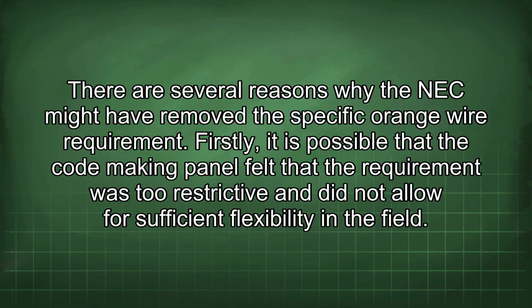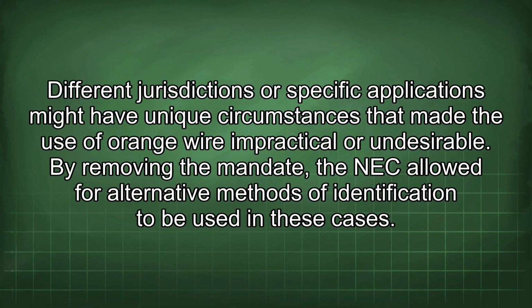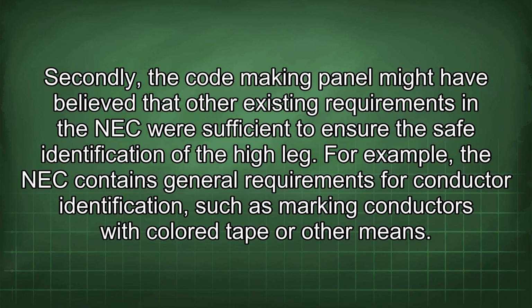There are several reasons why the NEC might have removed the specific orange wire requirement. Firstly, it is possible that the code-making panel felt that the requirement was too restrictive and did not allow for sufficient flexibility in the field. Different jurisdictions or specific applications might have unique circumstances that made the use of orange wire impractical or undesirable. By removing the mandate, the NEC allowed for alternative methods of identification to be used in these cases. Secondly, the code-making panel might have believed that other existing requirements in the NEC were sufficient to ensure the safe identification of the high leg.